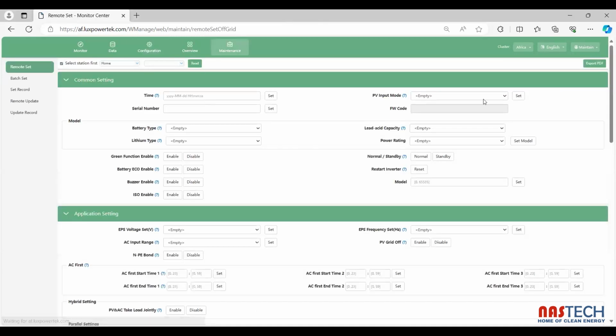A second issue is that because these units are all in remote areas, when there is something wrong, we cannot see the logs. So we don't see the history of the unit because they are not connected to the internet. So it is very difficult.